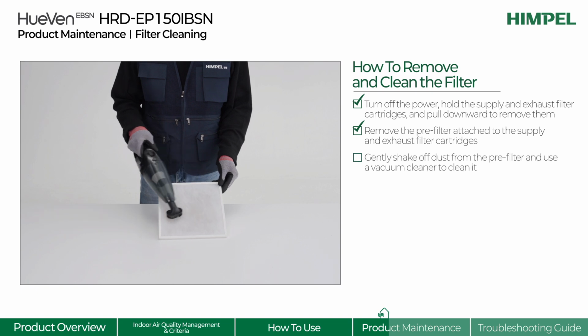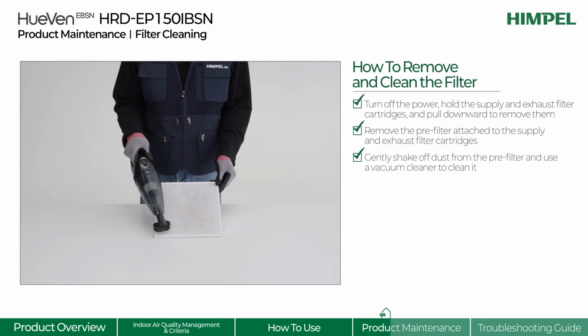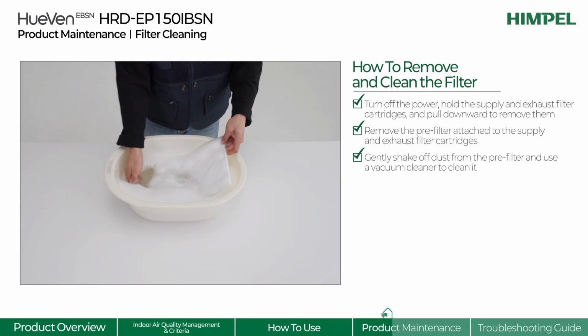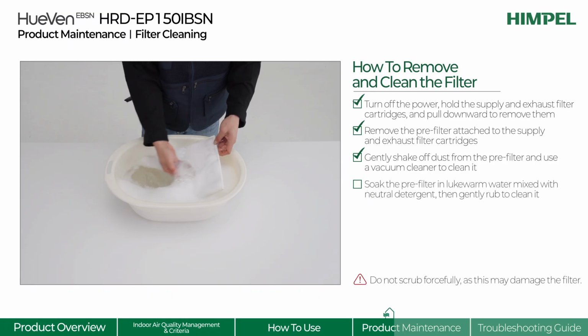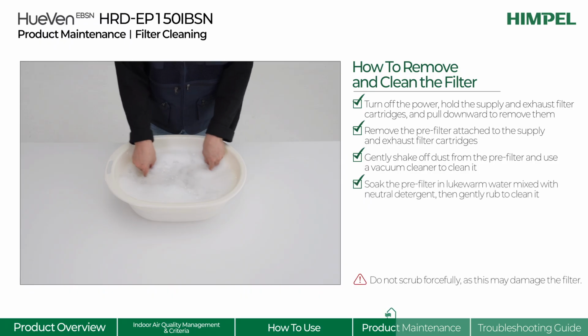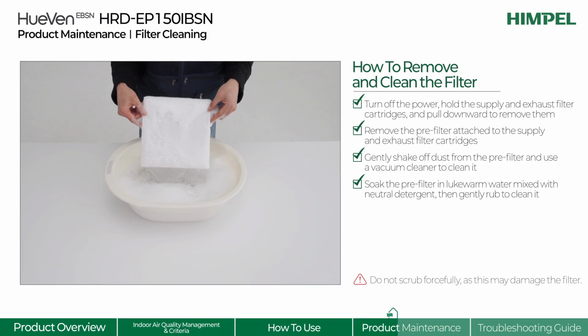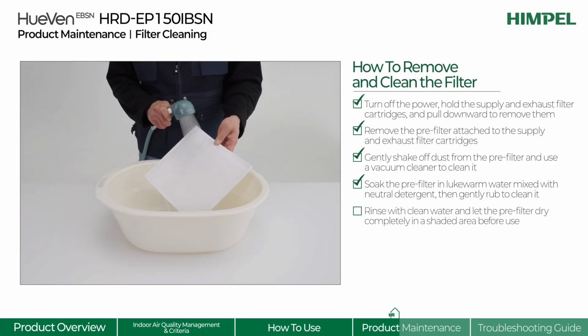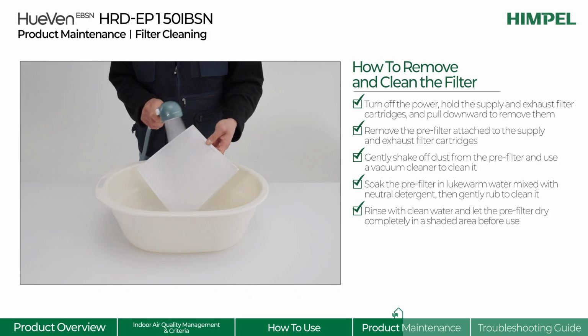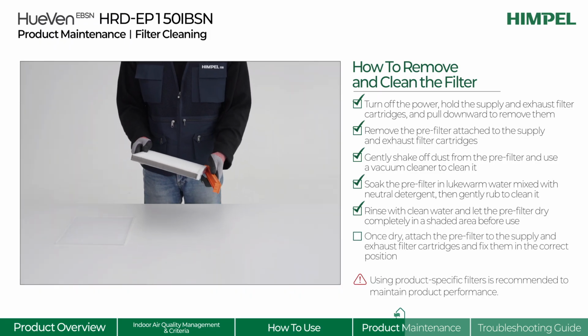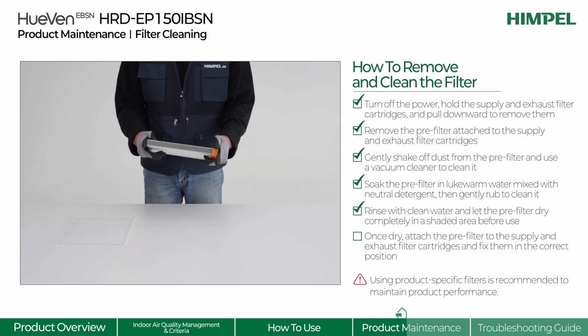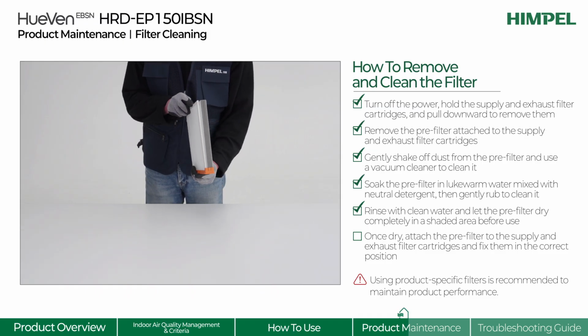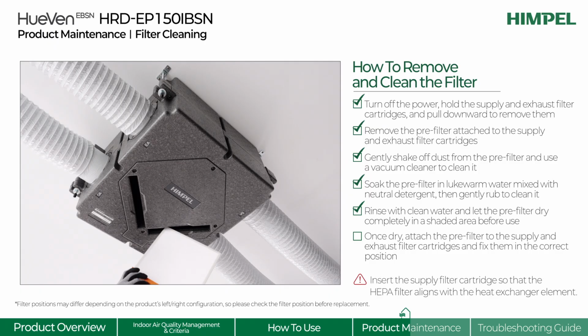Once the pre-filter is removed, use a vacuum cleaner to remove any dust. Soak the pre-filter in lukewarm water mixed with neutral detergent and gently rub to clean it. Rinse the pre-filter with clean water and let it dry completely in a shaded area before use. Once dry, attach the pre-filter to the supply and exhaust filter cartridges and fix them in the correct position.